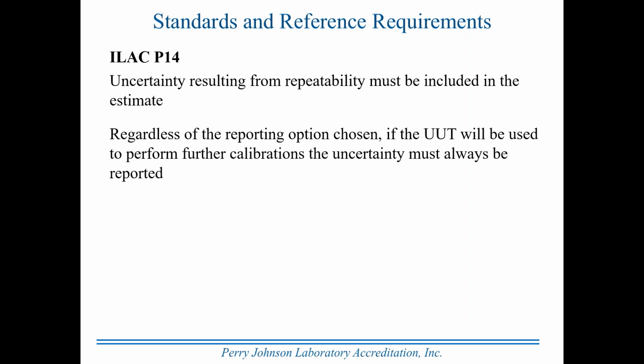Regardless of the reporting option chosen, and this is somewhat a holdover from the 2005 version of the standard, if the unit under test will be used to perform further calibrations, the uncertainty must always be reported. Under 2005, which some laboratories are still operating under until they transition prior to November 29th, so we need to mention this. If the device being calibrated will itself be used to perform further calibrations, then it's mandatory that the uncertainty be on the certificate. If it will not be used for further calibrations, then the uncertainty has to be estimated and either reported on the certificate, or it can be used to make a statement of compliance with specification.